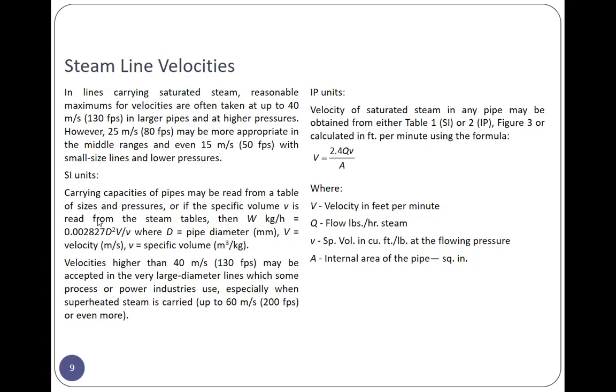So SI, carrying capacities of pipe may be read from a table of sizes and pressure. Or if the specific volume v is read from the steam table, then W in kilograms per hour is 0.002827 D squared v over V, where D is diameter in mm, v is the velocity in meters per second, and V is the specific volume in cubic meters per hour.